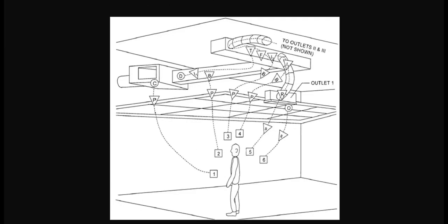Let's do a simple example in acoustical modeling. Let's say that we have a fan-powered terminal unit in a plenum above a ceiling grid with a rectangular discharge which has a T and two flex connections to two diffusers with only one serving the occupied space of this model. This is all open occupied space, with occupants directly underneath the terminal unit. In this example, there are 6 separate paths of sound to perceive by the perceiver's ear.